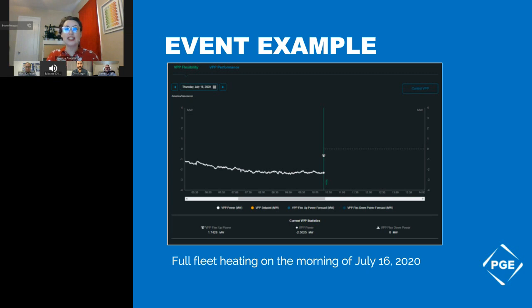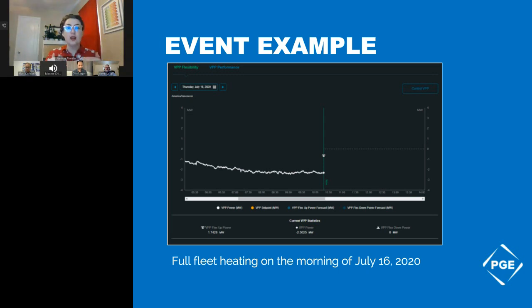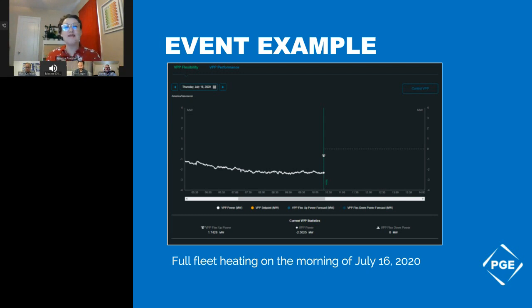This is what all those water heaters look like when you put them into an event on Enbala's Concerto platform — a virtual power plant where assets, the water heaters, can be associated to different groups. The example shown is every single water heater in our fleet actively heating on the morning of July 16th. On this platform, zero means no heating; above zero would mean absorbing energy onto the grid, like a battery; below zero means the water heater is using power. This is what actively heating looks like — a lot of up-and-down movement, definitely below zero.